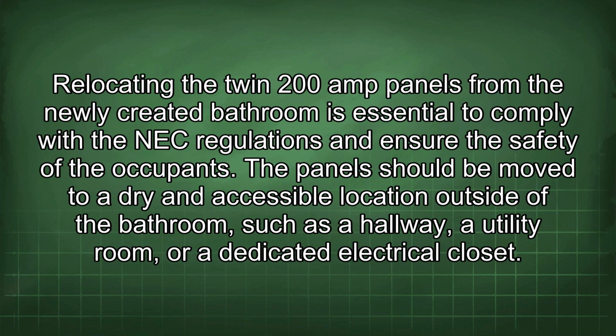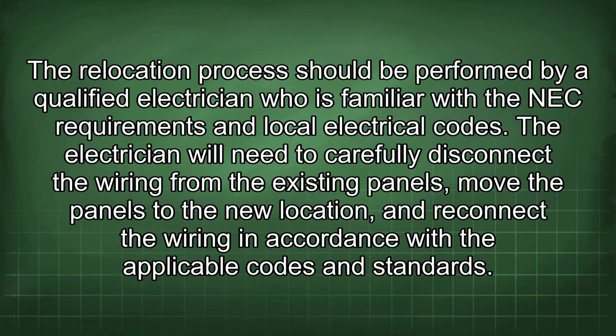Relocating the twin 200-amp panels from the newly created bathroom is essential to comply with the NEC regulations and ensure the safety of the occupants. The panels should be moved to a dry and accessible location outside of the bathroom, such as a hallway, a utility room, or a dedicated electrical closet. The relocation process should be performed by a qualified electrician who is familiar with the NEC requirements and local electrical codes. The electrician will need to carefully disconnect the wiring from the existing panels, move the panels to the new location, and reconnect the wiring in accordance with the applicable codes and standards.